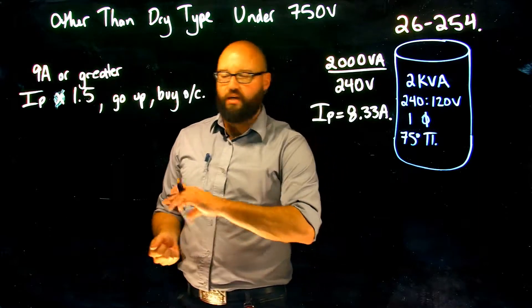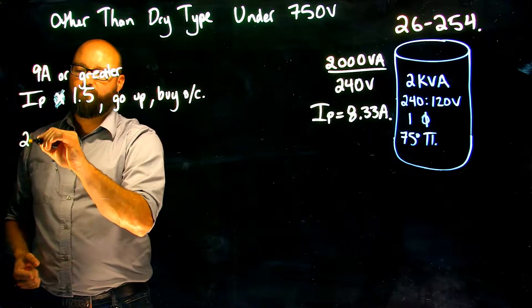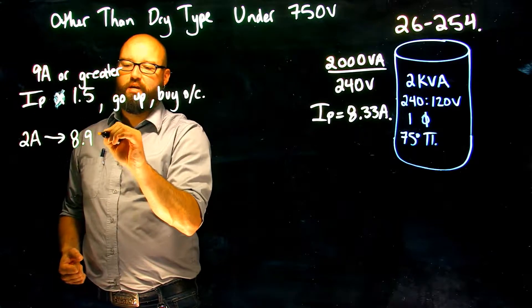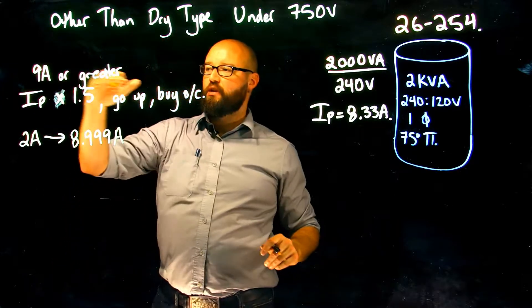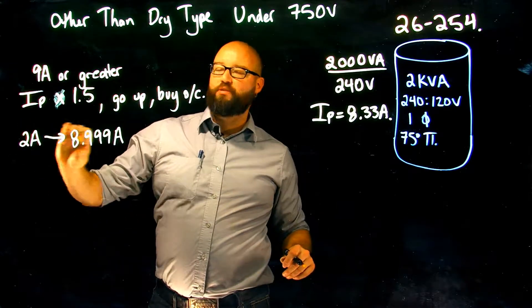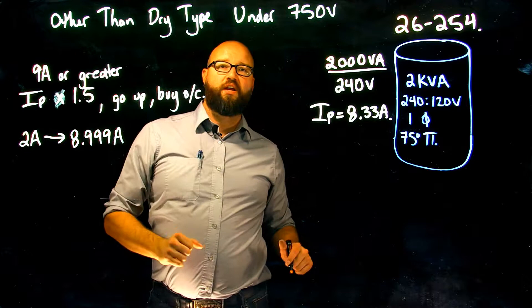And if I continue reading there's another exception that says if it's less than 2 amps. So let's write it like this: if it's from 2 amps up to 8.999 amps, because as soon as we hit 9 we're into the 150 percent. If it's between 2 amps and 8.999 amps, it tells me I cannot have an overcurrent rated or set at more than 167 percent.